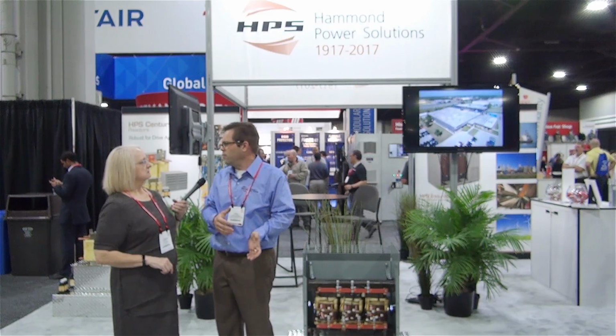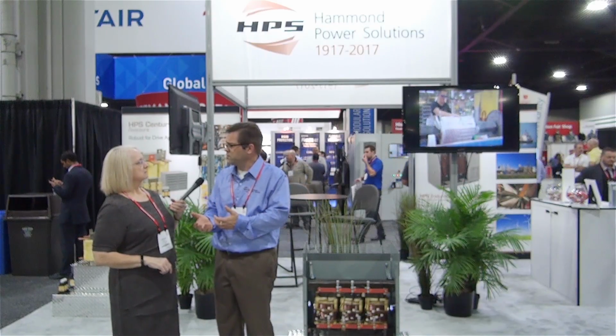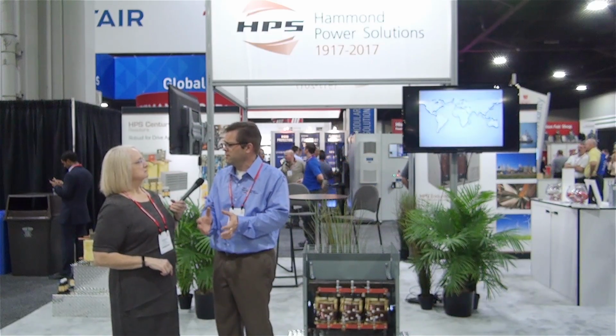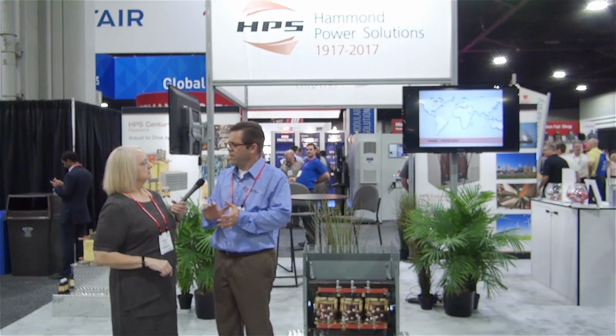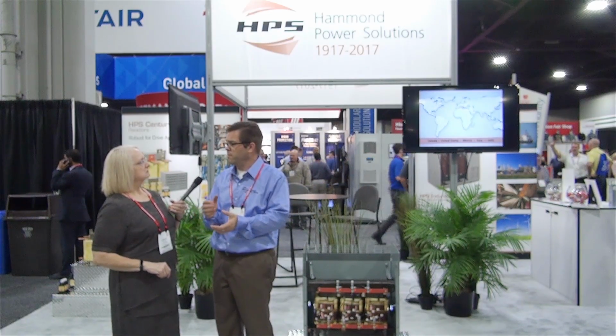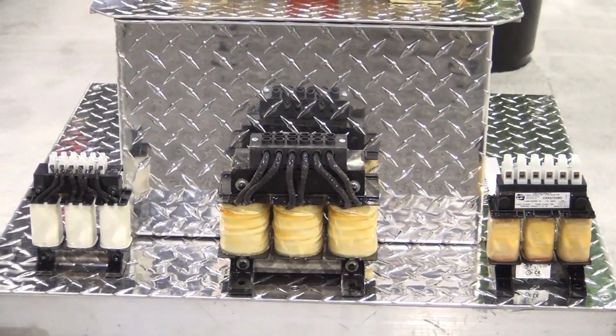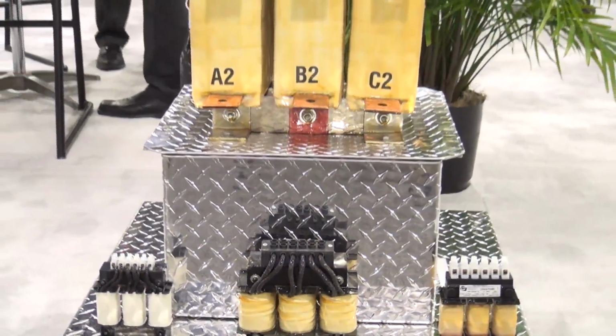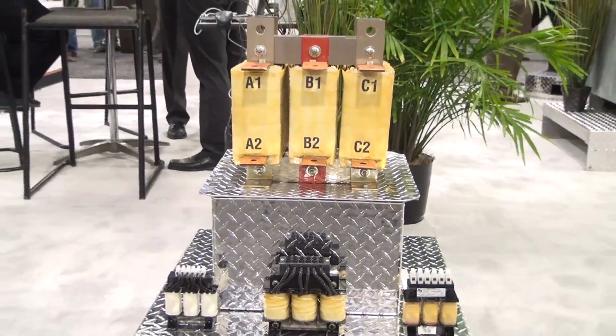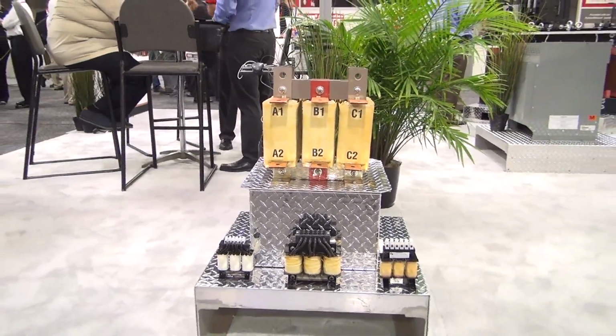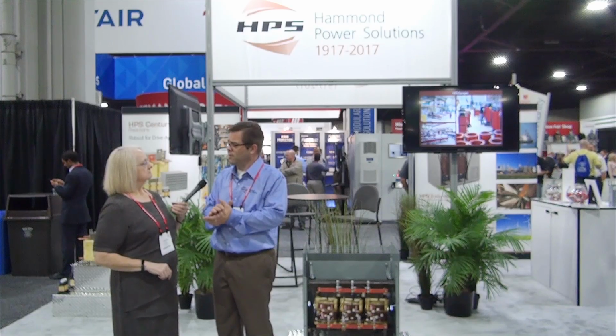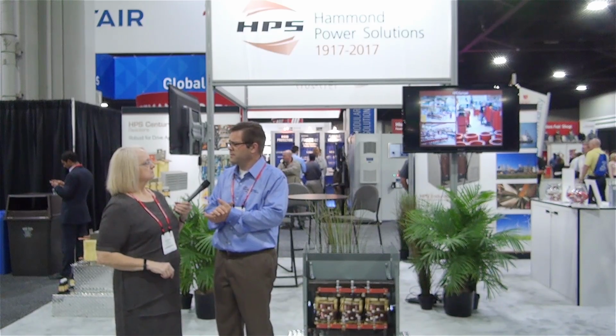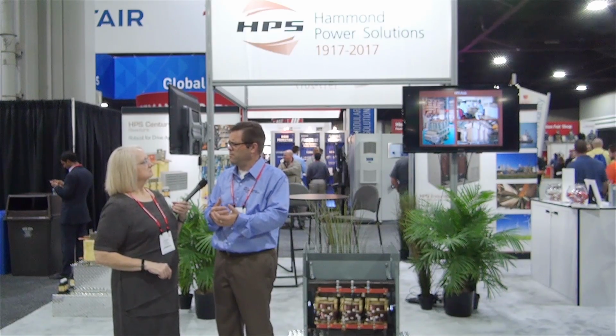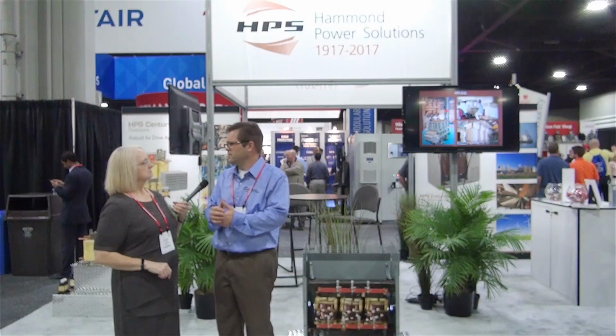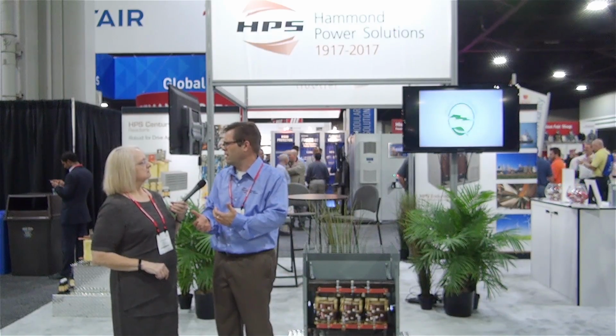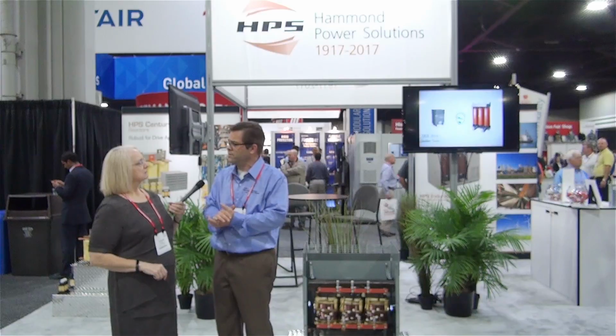Normally when we build our low voltage transformers, and some of our medium voltage as well, we just dip it into an insulation and bake it. With the casting process, we put a mold around the coils, which allows us to apply a much thicker supply of resin, fiberglass, and other materials. That thicker coating helps better protect the coils, makes the units physically smaller since I don't need as large air gaps, and also aids maintenance and cleaning. It can be put in much more aggressive environments without as many enclosure changes as we'd need with the VPI transformer.